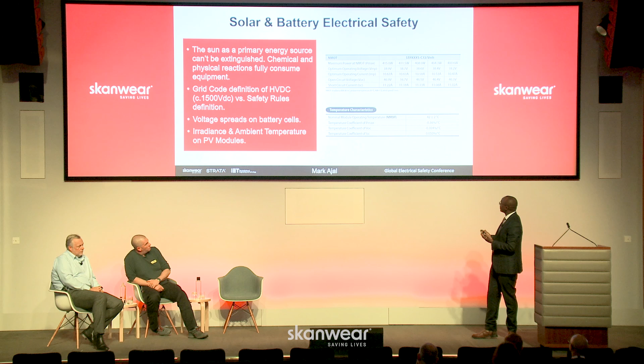So you've got an inverter, 1,500 volts. How many strings can you connect so that you don't exceed that voltage? It's not a simple addition of the strings. You need to calculate. There are 4 methods. I'll not touch on them in this, but we can have a session later where you do worst case combinations. What if we have this level of irradiance and the temperature drops? What impact would that have on my open circuit voltage? Those calculations help you determine how many strings to connect for the modules and how many strings to connect for your batteries. But it also helps you with specifying your inverters. So the inverter manufacturer will guarantee this inverter is safe up to this number of strings.